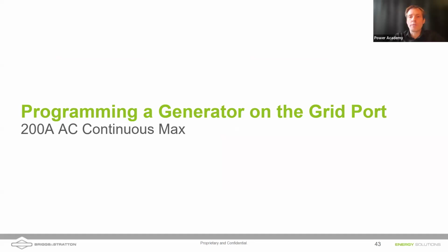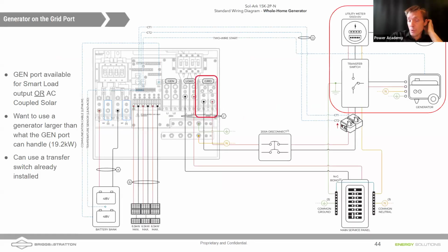If we're going to program a generator on the grid port, such as for an off-grid system, maybe the one that was being asked about at the beginning of the talk, or because we've got a transfer switch because we want to bring in a big generator like our 26K, and I want to have access to that full 112 amps of output, well, I'd be limited to 80 amps in the gen port. So if I use a transfer switch, I can bring the generator in through the grid port.